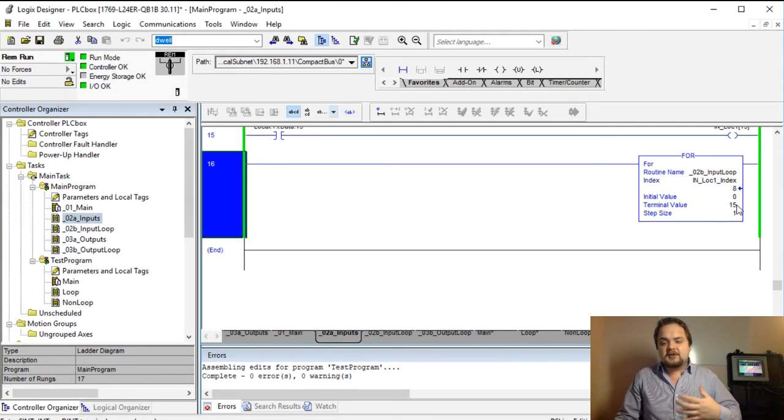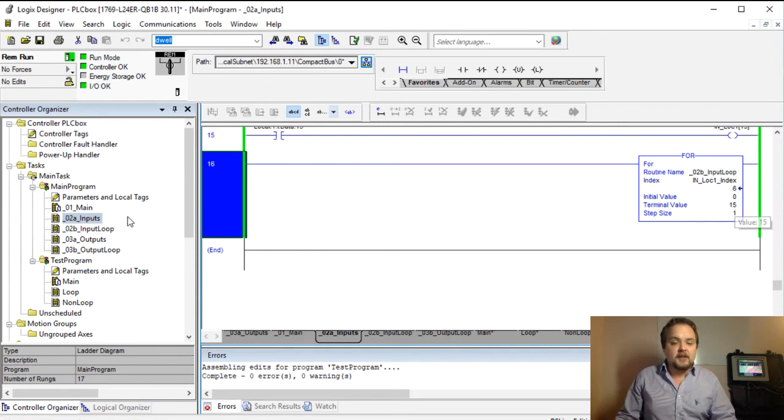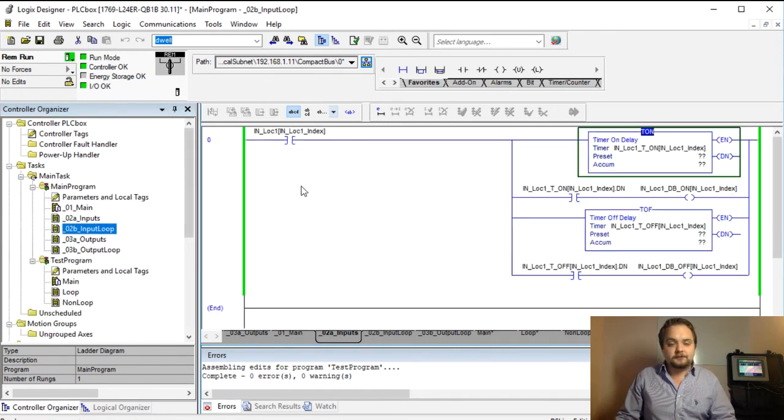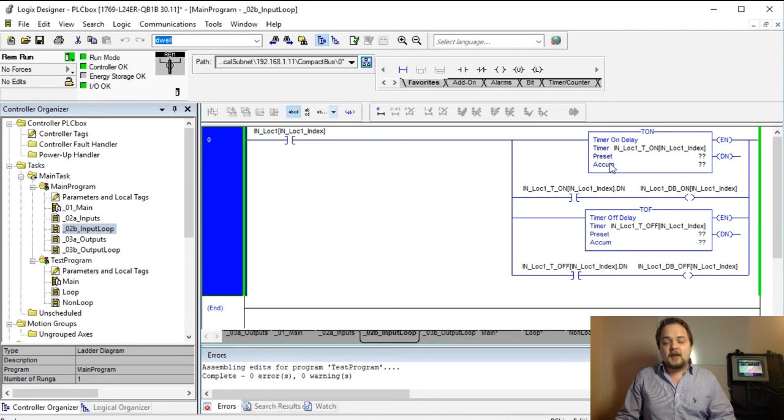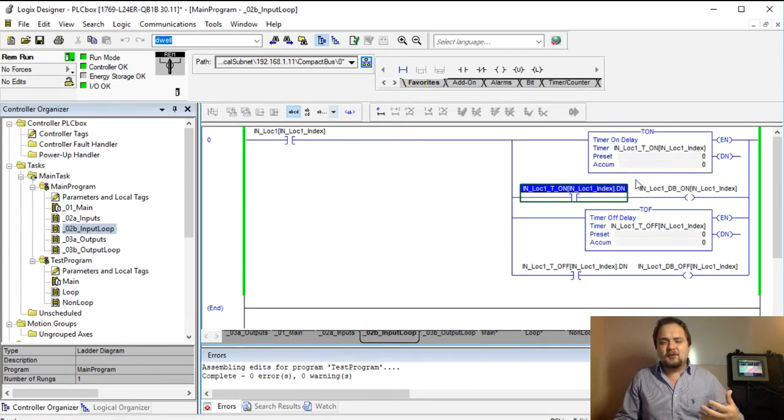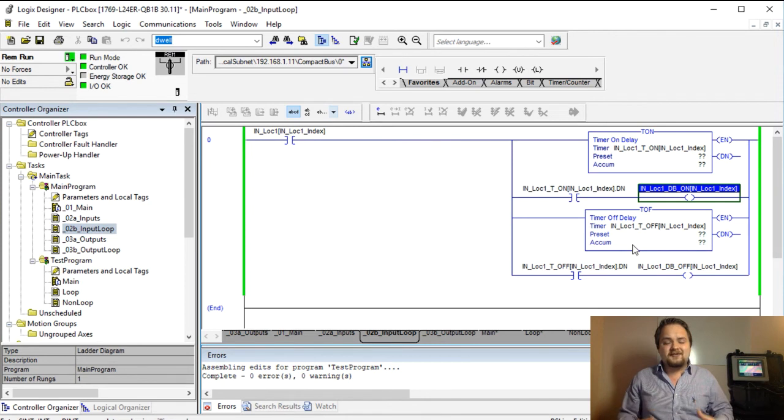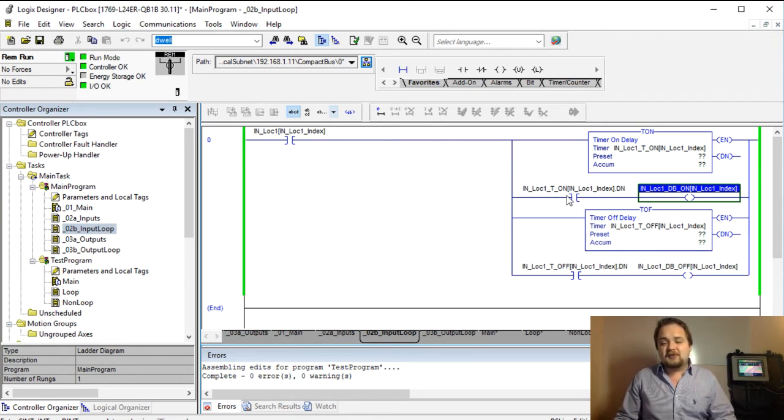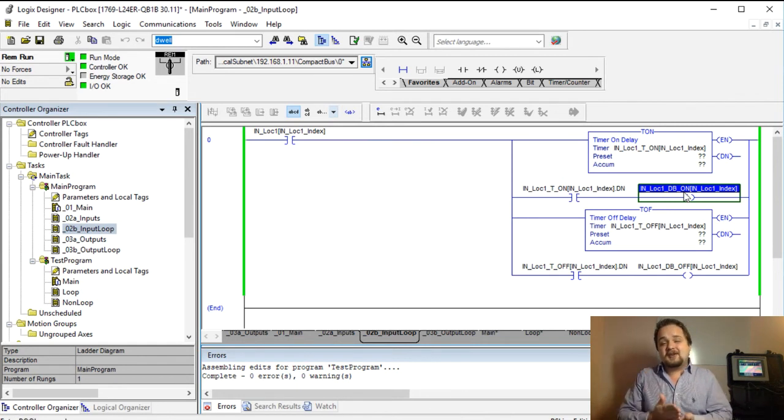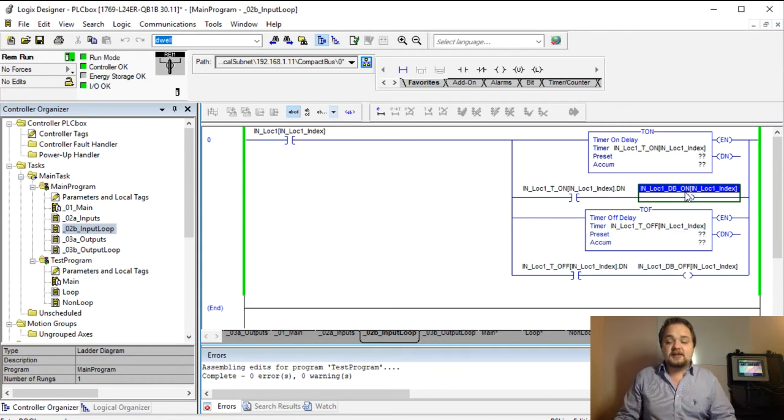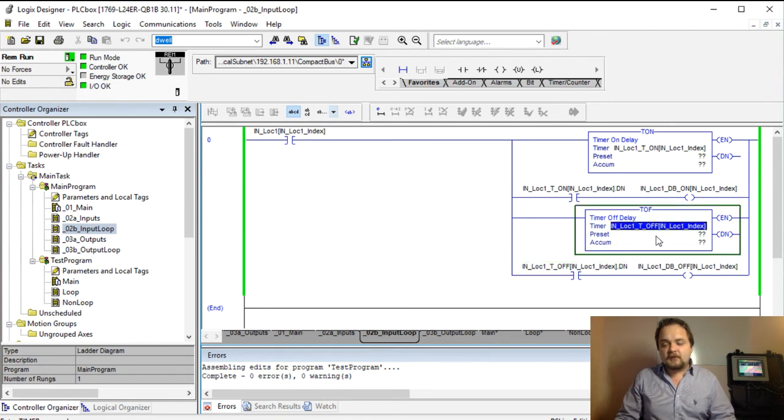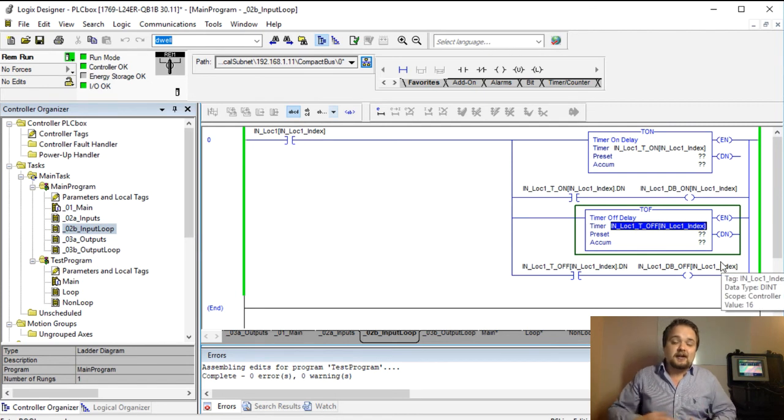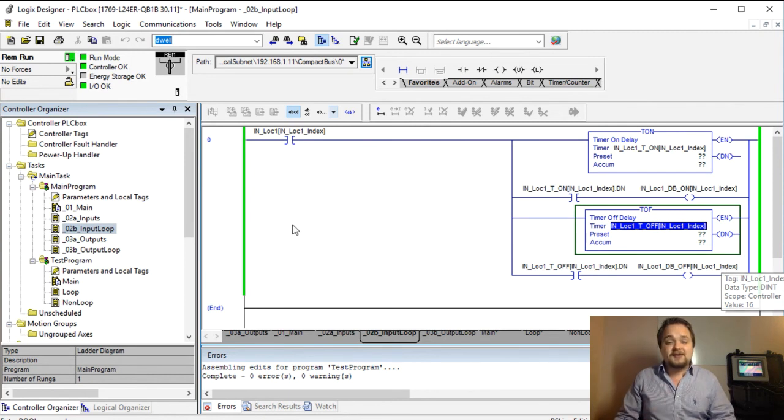That being said let's look at the input loop so in the input loop all I'm doing is I'm essentially creating that one timer I'm creating one that once the timer is done I am energizing that one bit therefore it's essentially very conveniently creating a structure which allows me to essentially create a timer on delay so the input comes in but then only 500 milliseconds later the actual bit is being set similarly if the input is being low so the timer off is activated timer off delay and then after 500 milliseconds that input is being de-energized and you can use this all over the program after it's been processed but as you can see this is only a single rung of code versus if I wanted to do that for every single input I would have had to copy that massive rung in here.